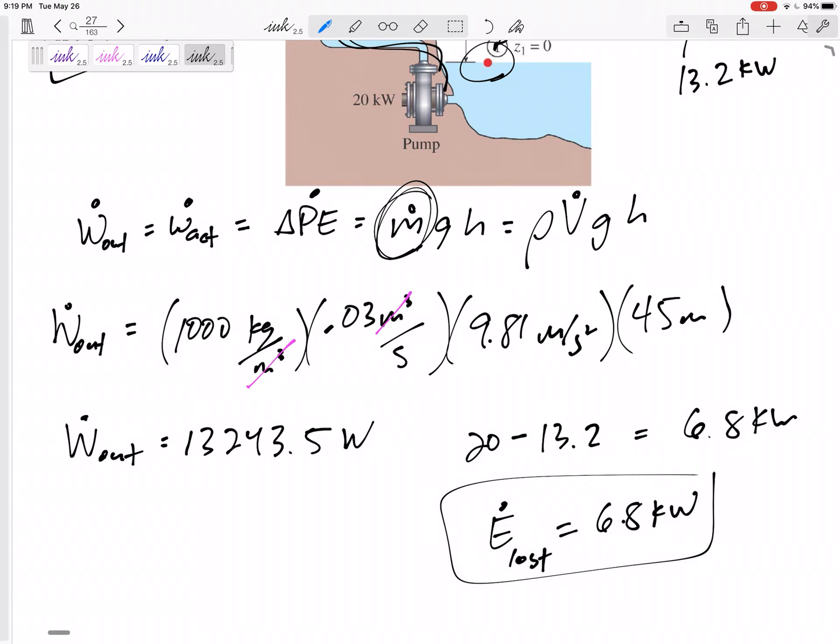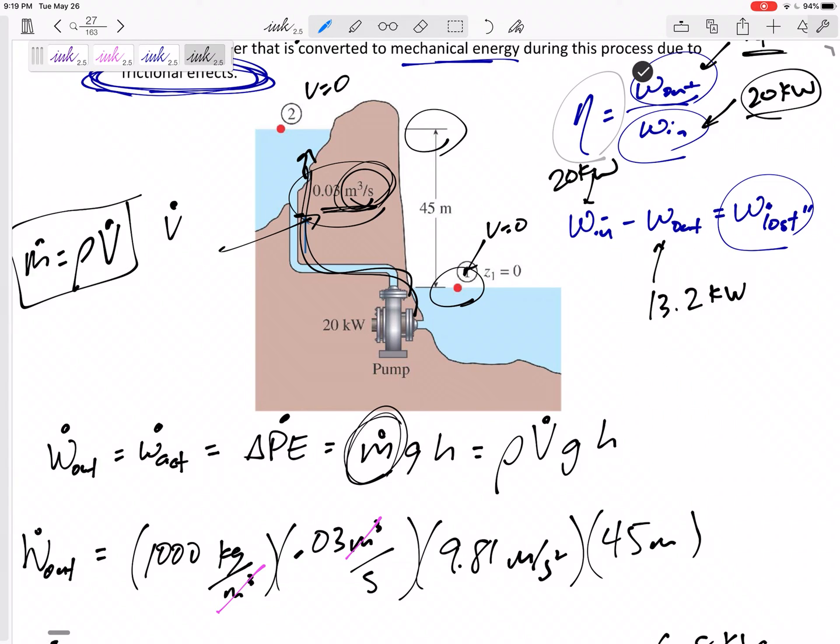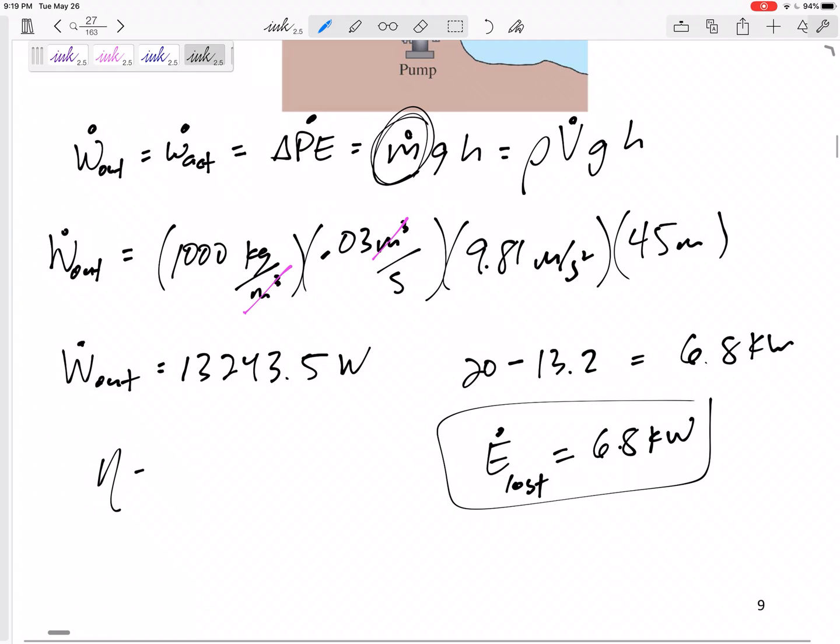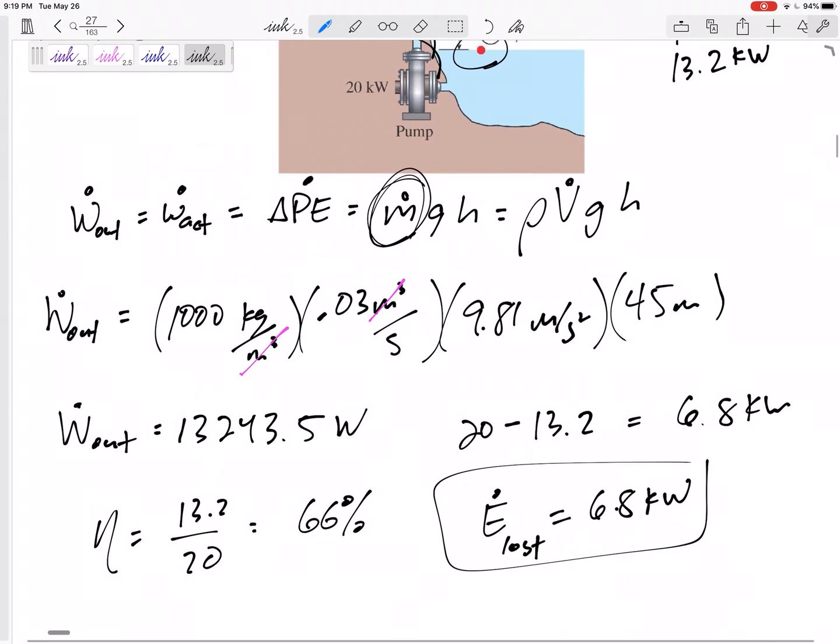Now, it didn't ask, but a lot of times it asks, okay, so what's the efficiency? What's the mechanical efficiency of this? The mechanical efficiency would be 13.2 over 20, about 66%, or 0.66 is the mechanical efficiency of that pump right there.